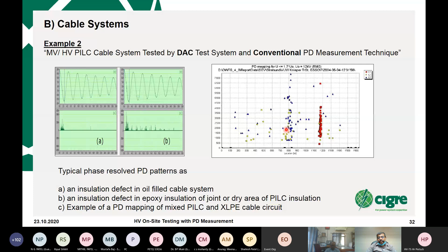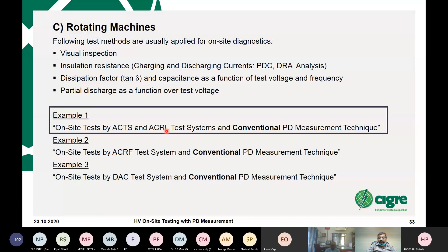The other example which is shown are rotating machines. Again, 3 examples are shown. Important is visual inspection as every time, insulation resistance in addition, and the power loss factor or dissipation factor, the capacitance as a function of test voltage and frequency. And in this case, you can test with different sources and with a conventional PD measurement test I would like to show. Next slide. Here you can see a rotating machine.